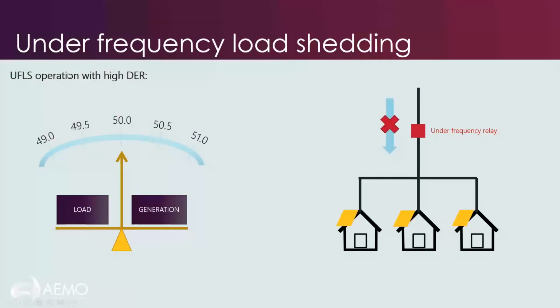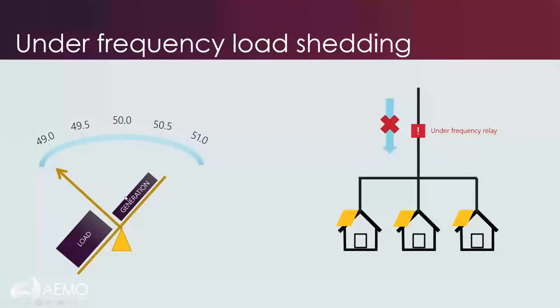Now, in a period with lots of distributed resources, we have potentially a lot of generation on this feeder that's supplying that local load, so there's no load on this grid. Now, when we see generation drop off, frequency will drop, the relay will still detect that and will still open the circuit, but we're not seeing a drop in load associated with that. So essentially, the under-frequency load shedding will not function under these conditions. We're not getting that restoration or the rebalancing of load and generation.